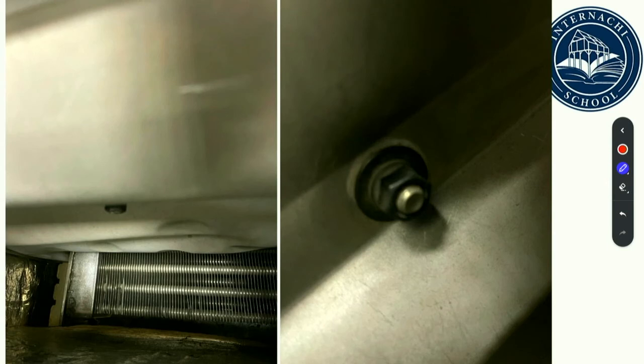So again, with the bolt. Out of curiosity, how long does it usually add to your furnace inspection to use a combustion analyzer? It takes us roughly 20 to 30 minutes to run this test on each furnace, so it does add time.